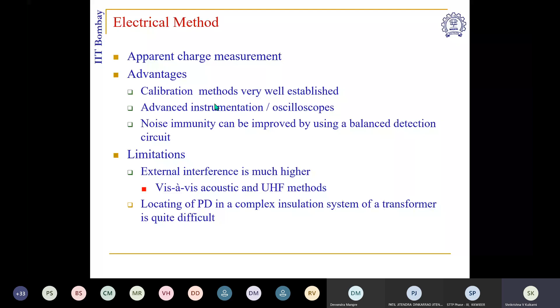The advantage of the electrical partial discharge technique is calibration methods are very well established. Advanced instrumentation and oscilloscopes are available, and noise immunity can be improved by using what is called a balanced detection circuit. But the limitations are the interference can be much higher, and locating partial discharge can be a challenge.